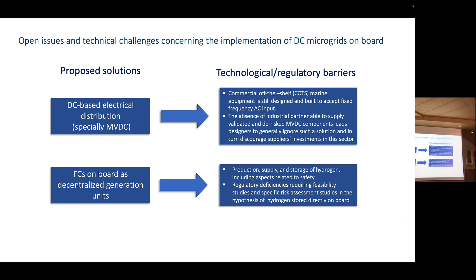Other main open issues in the implementation of DC microgrids on board are stability and protection issues. As for stability, ship power systems are always weak grids with low inertia and limited generation capability, so power imbalance can easily lead the system to instability. The solution requires a suitably controlled energy storage system and careful consideration of voltage stability, starting from small-signal and large-signal analysis.